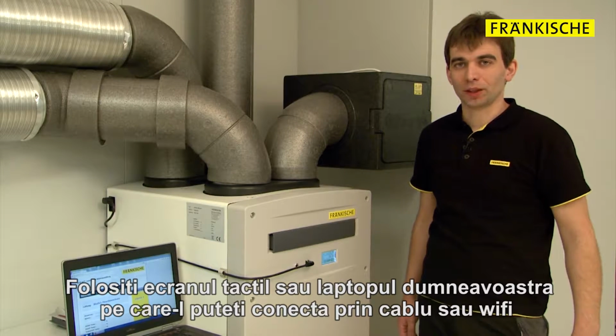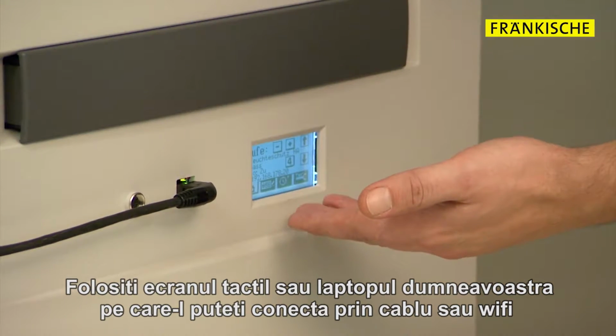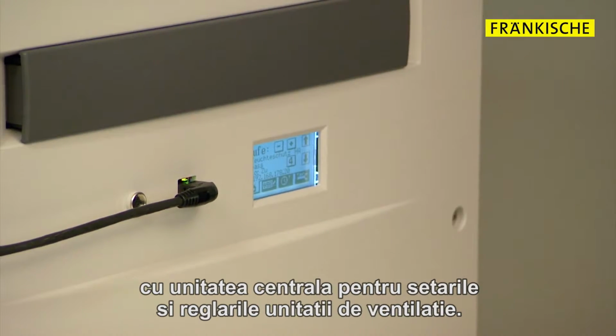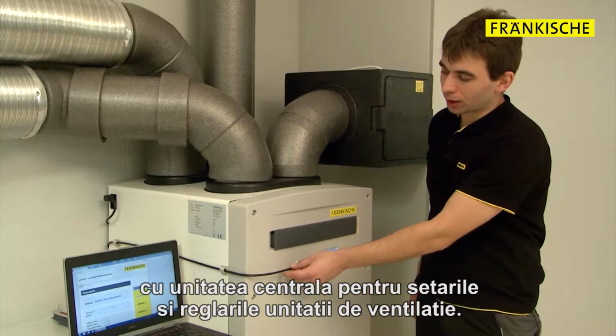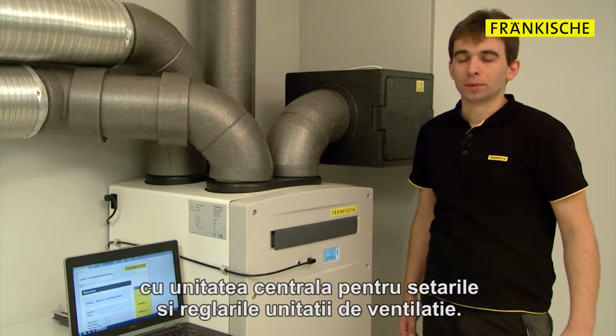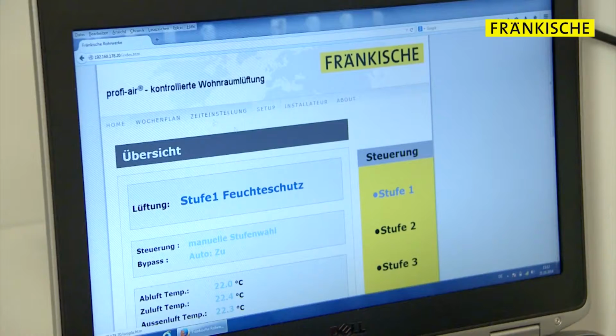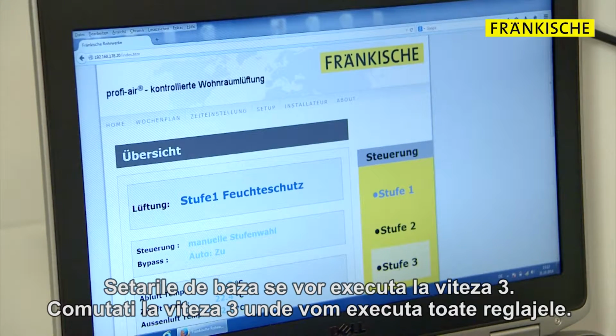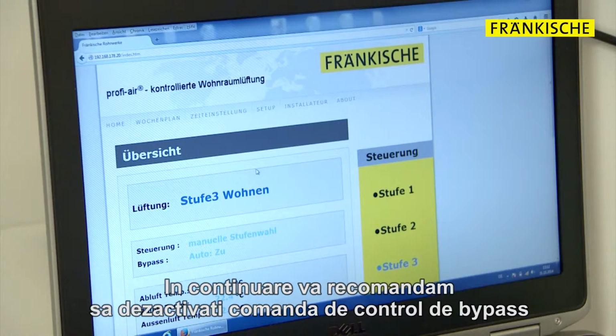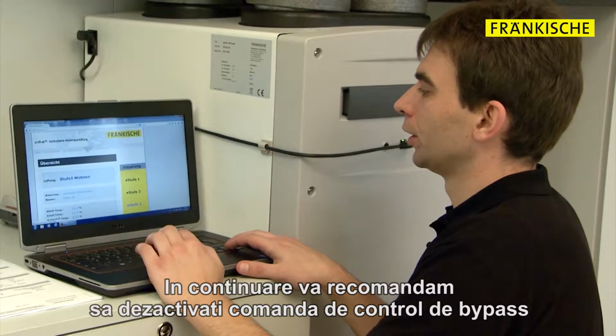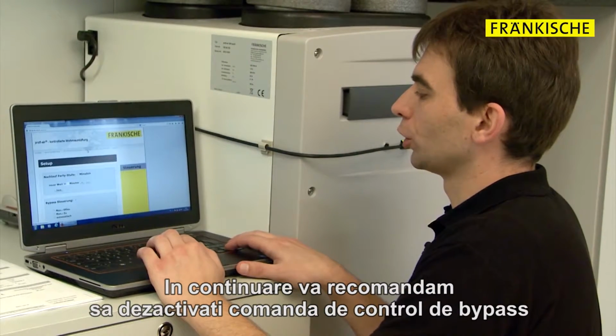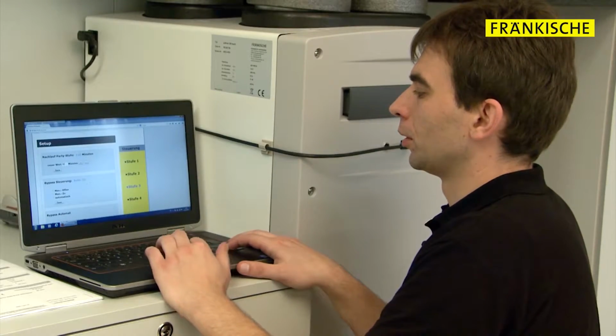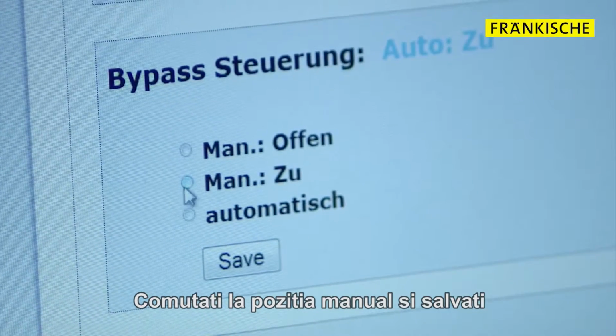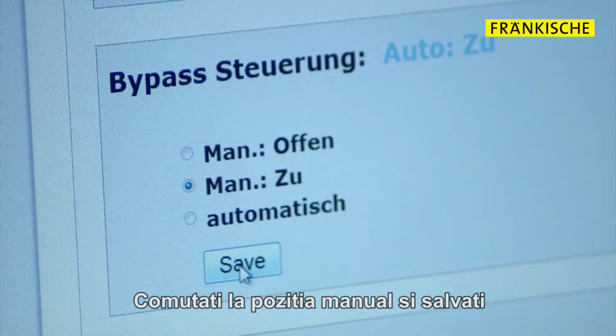Use the touch display or your laptop using a wireless or wired connection to configure the basic settings of the ventilation unit. The basic settings include switching to fan speed level 3, at which we would like to make all following measurements. Next, we recommend that you deactivate the bypass control. Switch to manual control and press Save to confirm.